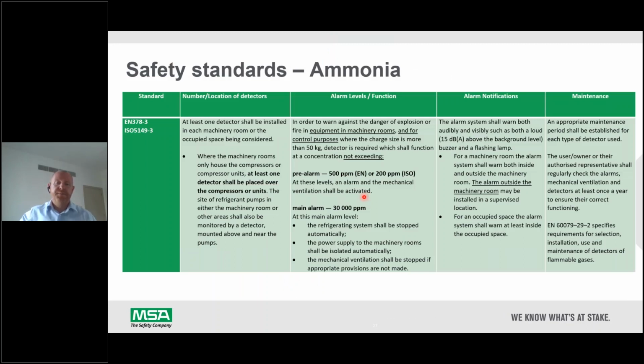Then we have separate safety standards for ammonia. So there's quite a lot to read here. I've just highlighted the main points. This standard, EN 378 and ISO 5149, says you need to put at least one detector over the compressors. Because ammonia is lighter than air, it goes to the ceiling. A detector over the compressors will detect that gas, because the compressor is the thing that vibrates the most and is one of the areas you're most likely going to get a leak.